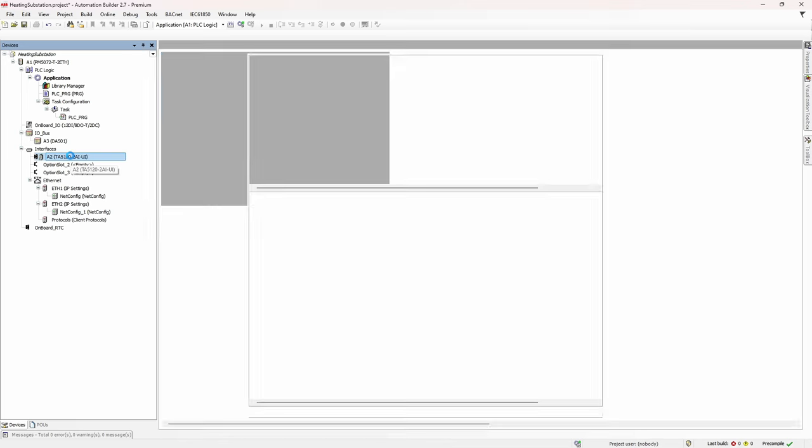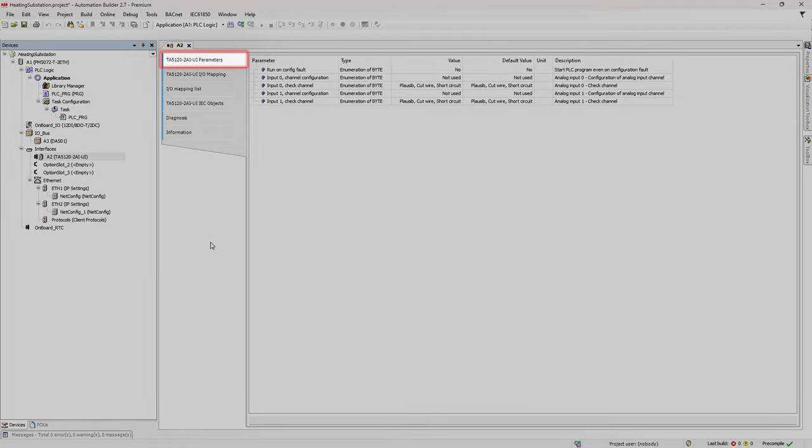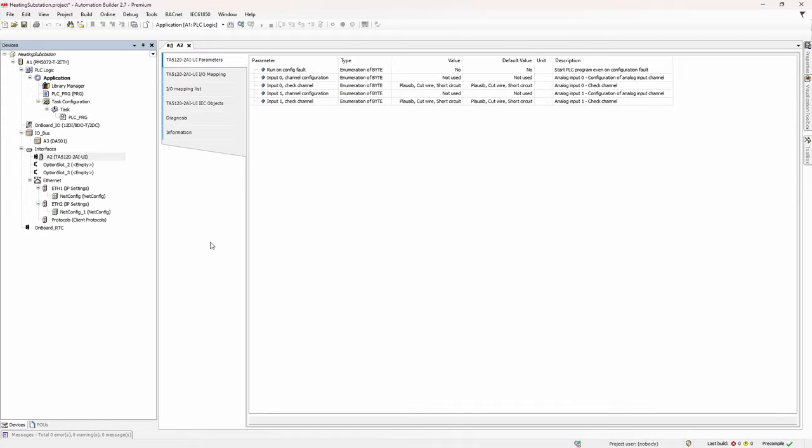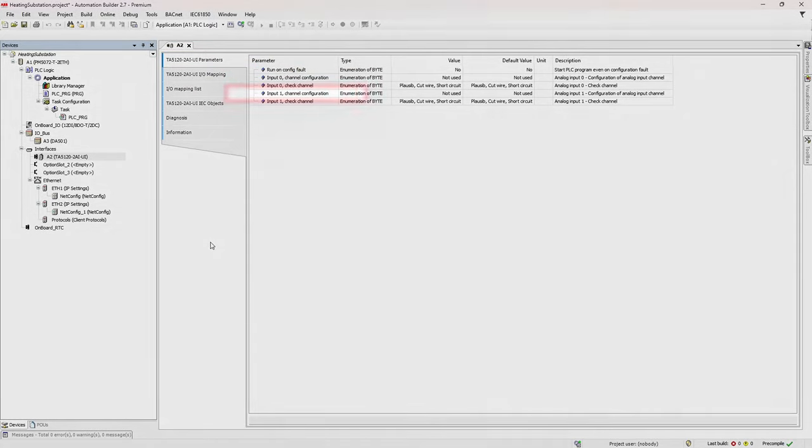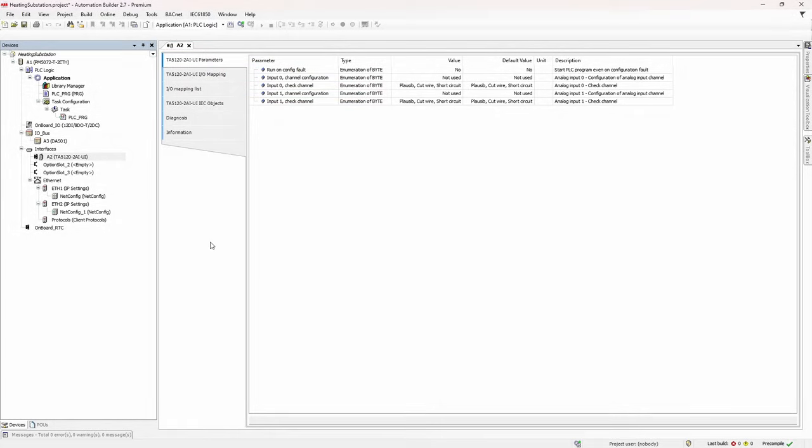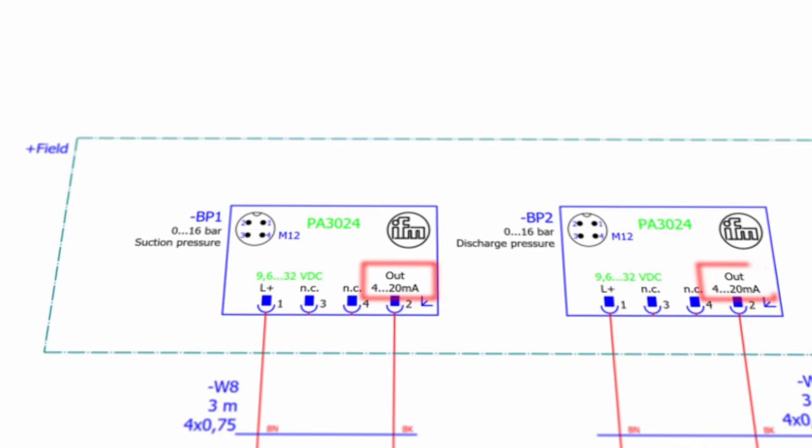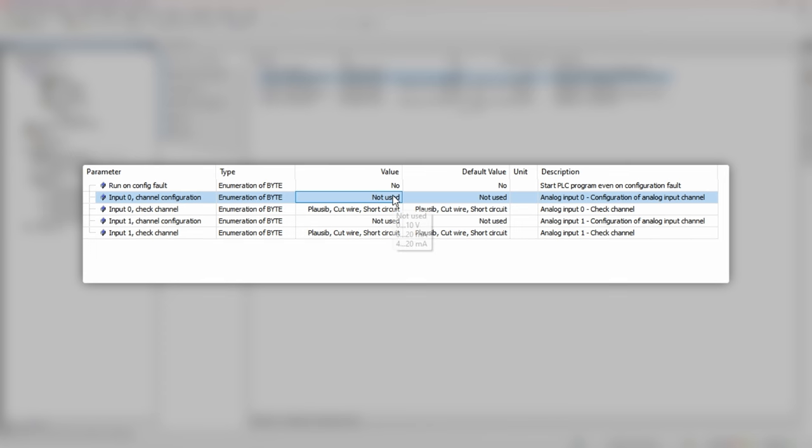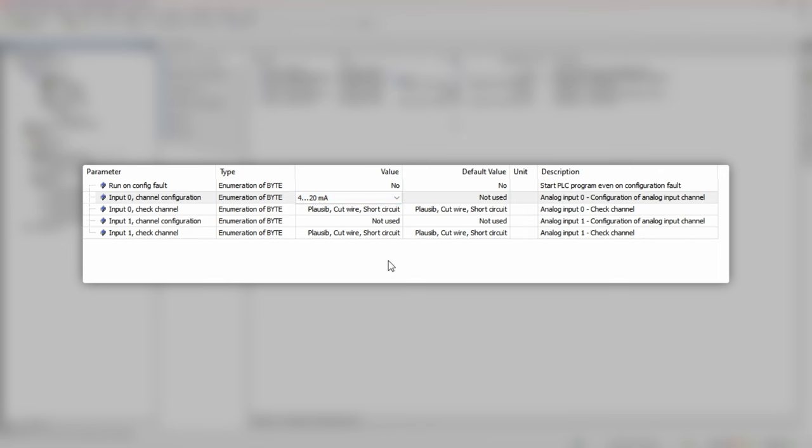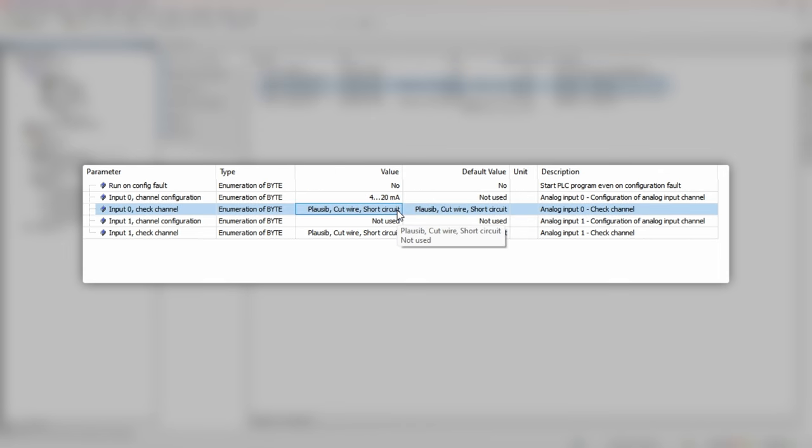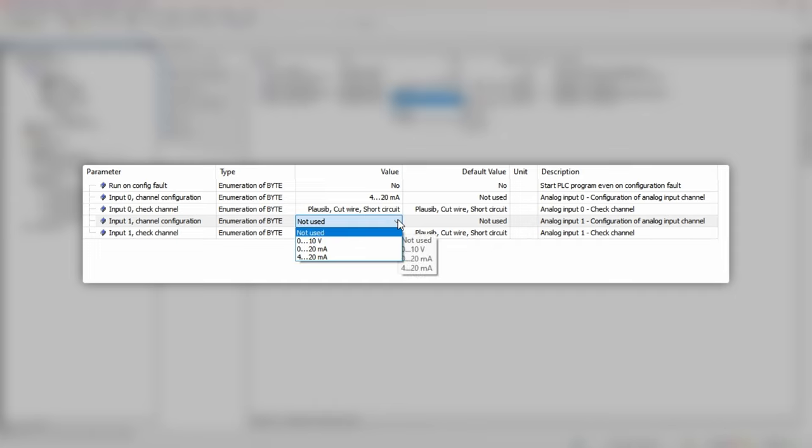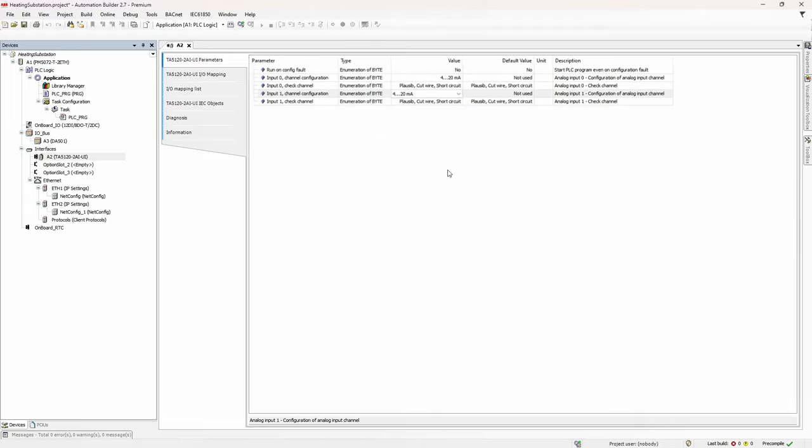Now we need to configure analog IO channels properly because by default all analog IO channels are not activated and will not work. So double click on A2 module and in the vertical tab parameters, we have channel configuration parameters for input 0 and 1. As you can see, default value is set to not used. So we need to change it to the type of signal which is coming from the transmitter. In our case it's 4-20 mA current signal. Check channel parameter will define whether module reacts or not to the transmitter's short circuit or wire cut. By default this option is enabled.